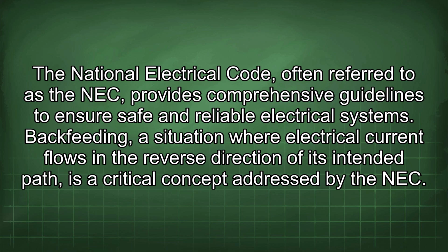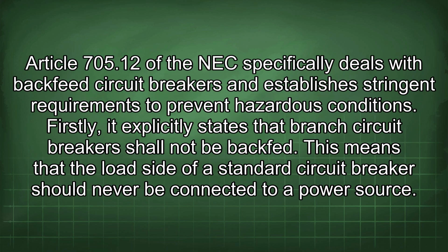Backfeeding, a situation where electrical current flows in the reverse direction of its intended path, is a critical concept addressed by the NEC. Article 705.12 of the NEC specifically deals with backfeed circuit breakers and establishes stringent requirements to prevent hazardous conditions. Firstly, it explicitly states that branch circuit breakers shall not be backfed. This means that the load side of a standard circuit breaker should never be connected to a power source.